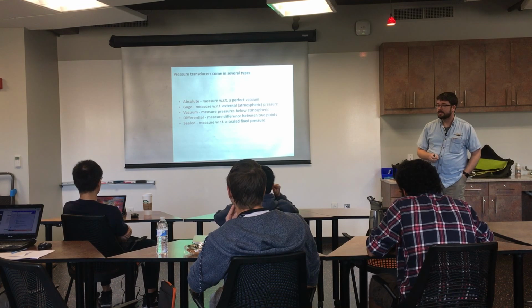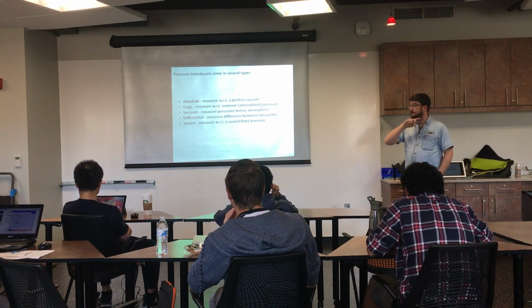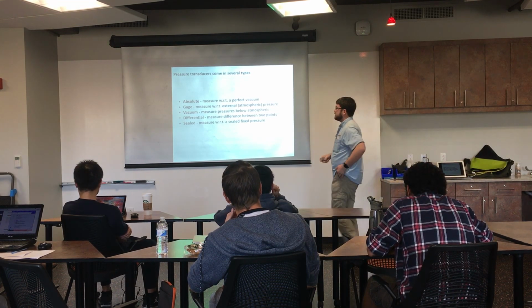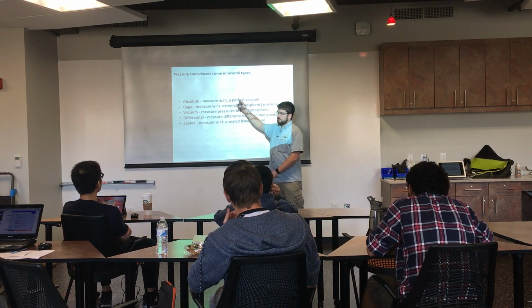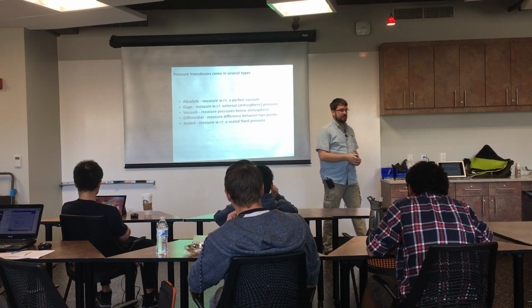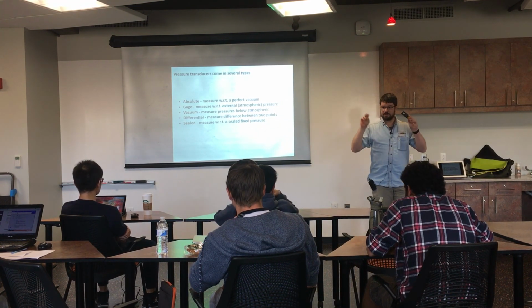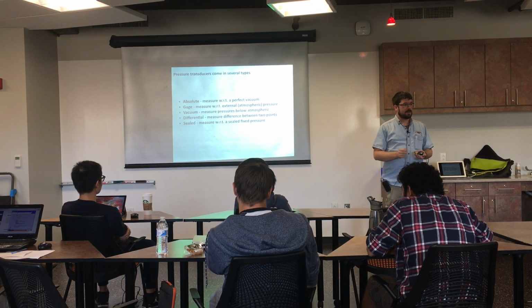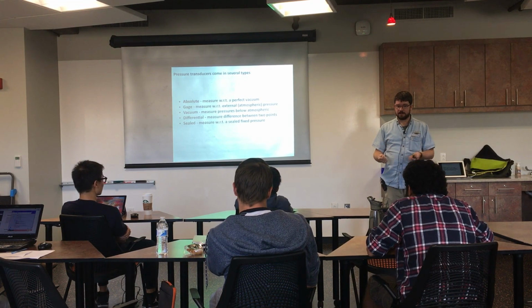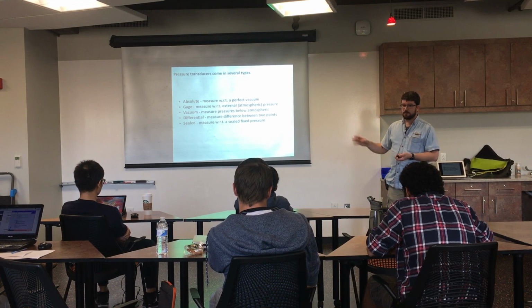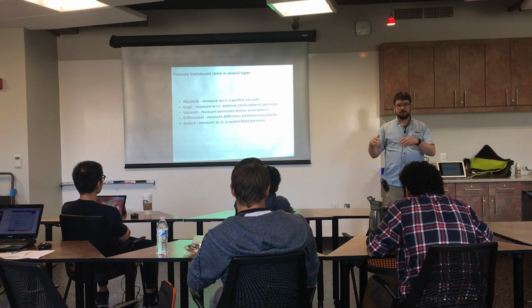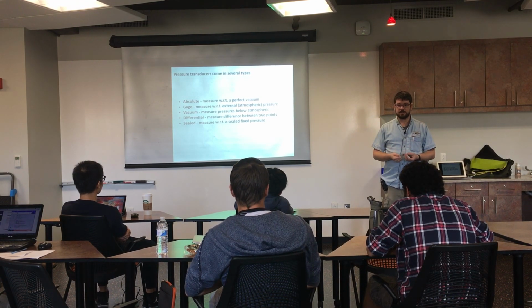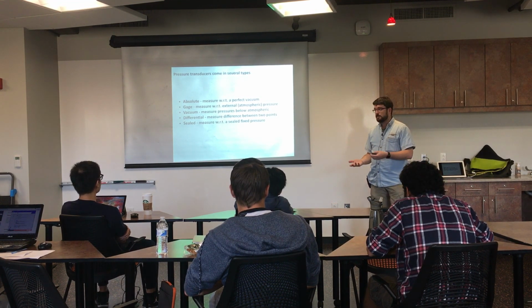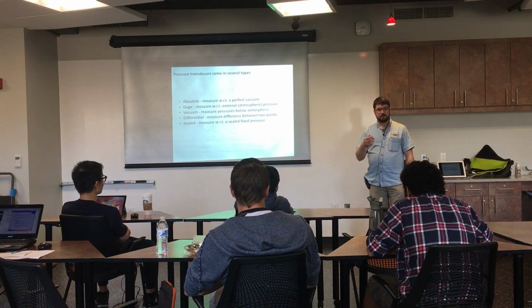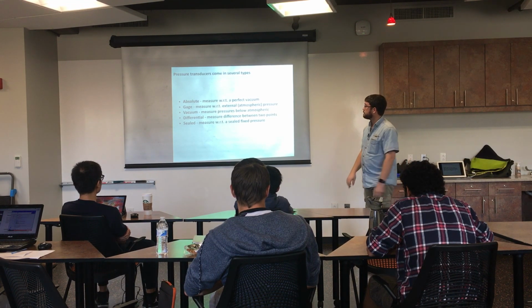Okay, pressure. Pressure transducers are a place, again, where a lot of terminology can trip people up. There are absolute pressure transducers, which tell you what the pressure is with respect to a perfect vacuum, ideally. So if we had an absolute pressure transducer right here, and were to project it on the board, it would say 900 and something hectopascals pressure, because that's what the atmospheric pressure here is right now. If we took it to sea level, it should be 101,325 pascals, because that's sea level pressure.